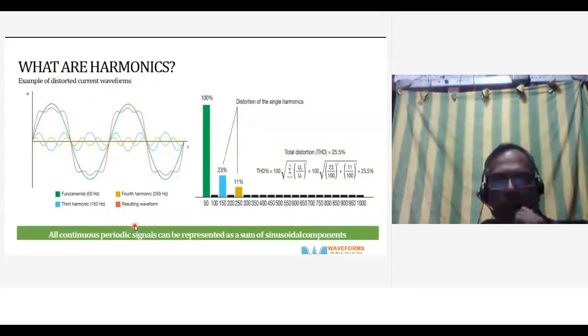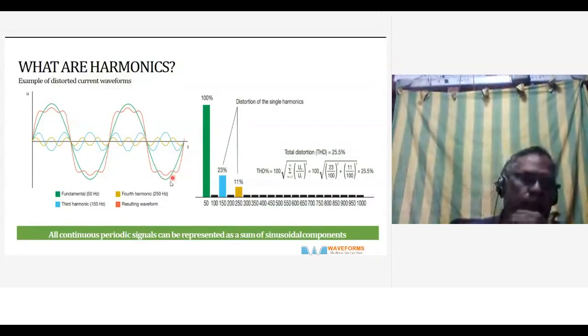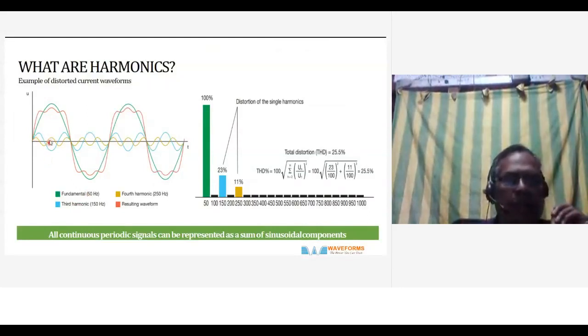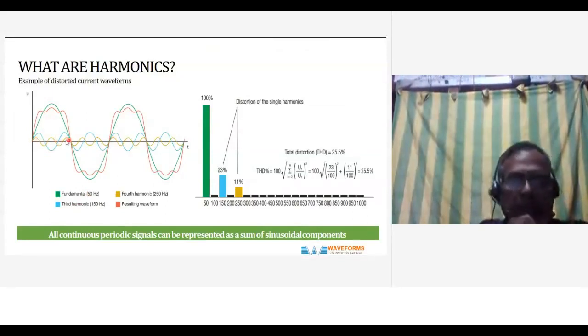So what are harmonics? Typically the fundamental waveform is 50 Hz. You see that blue waveform, green color waveform, which is a sine wave. Okay, that is the 50 Hz sine wave. But you will also see the third harmonic, which is in blue, which is 150 Hz. So you will find three waveforms in one cycle. So that is the third harmonic. Then you have the fifth harmonic, that is 250 Hz.